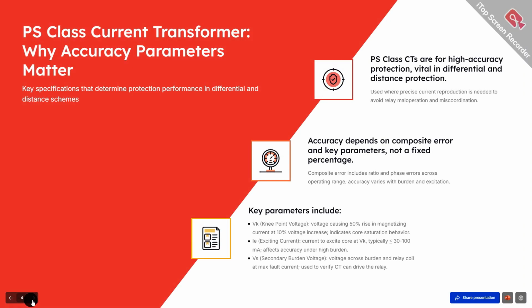PS class. This is a special protection class. Here you can see high accuracy protection, mainly used in differential and distance protection. In the earlier case we know what is the maximum error. Here we don't know the maximum error as said by 5P10 or 0.2 class. So how we calculate means we calculate based on the VK knee point voltage. We already know what is knee point voltage.